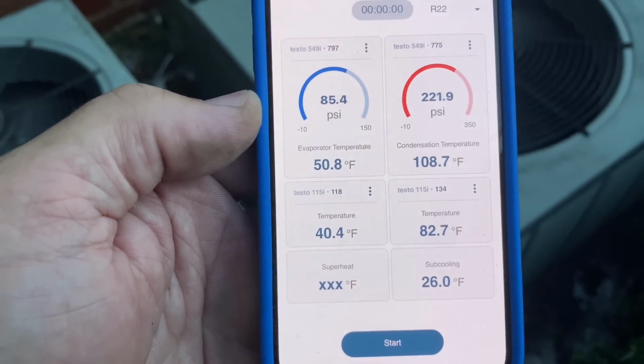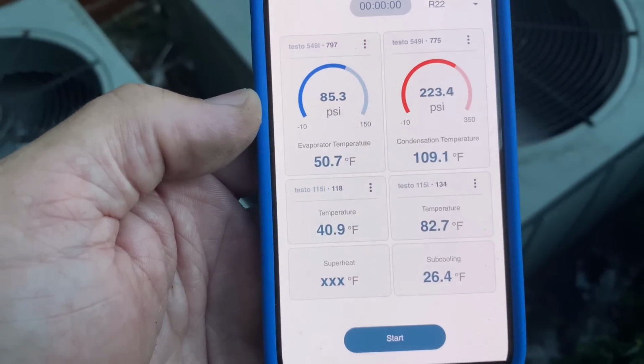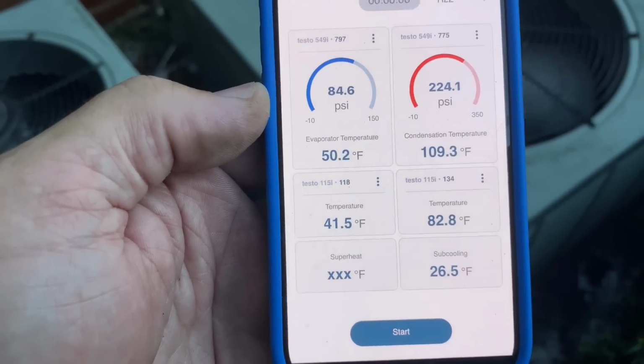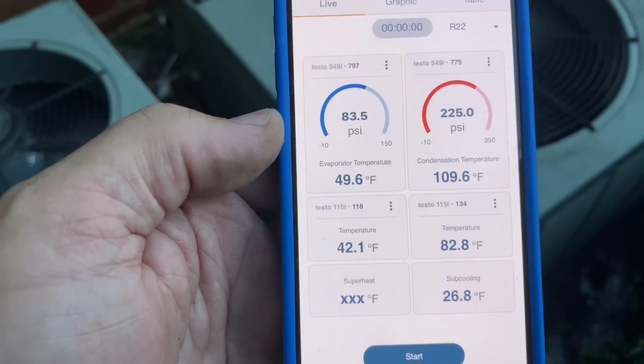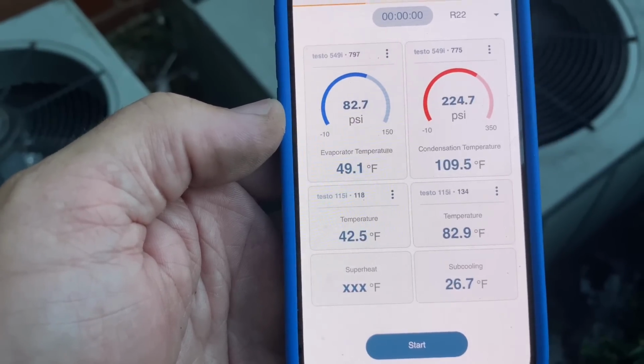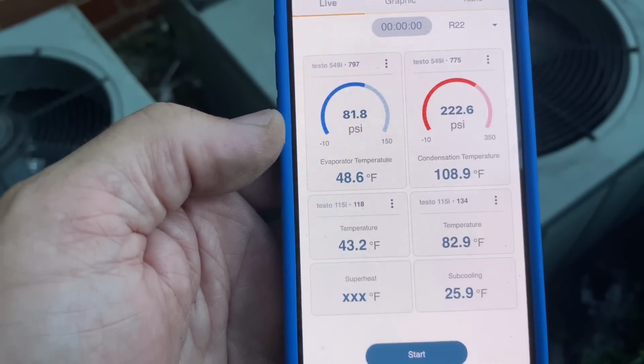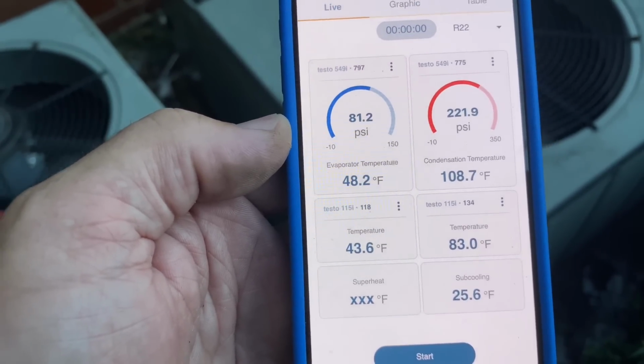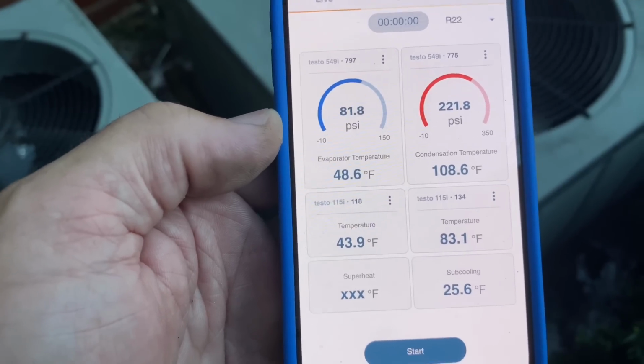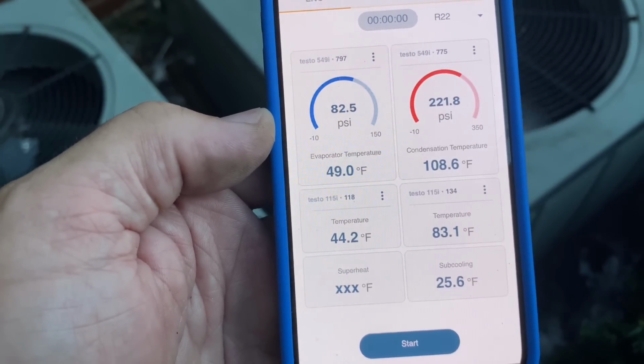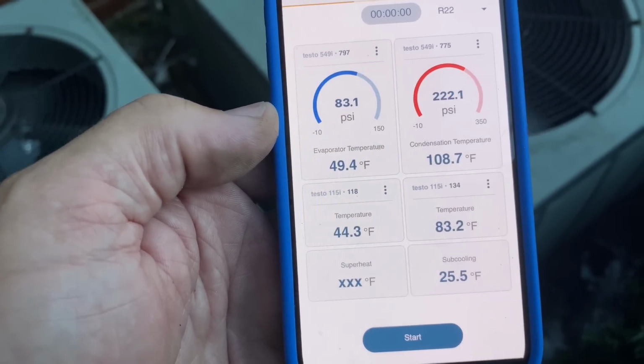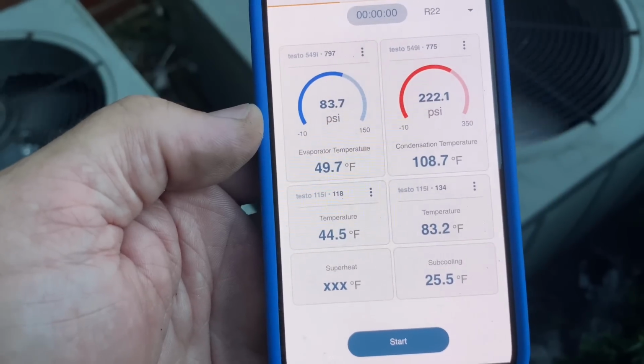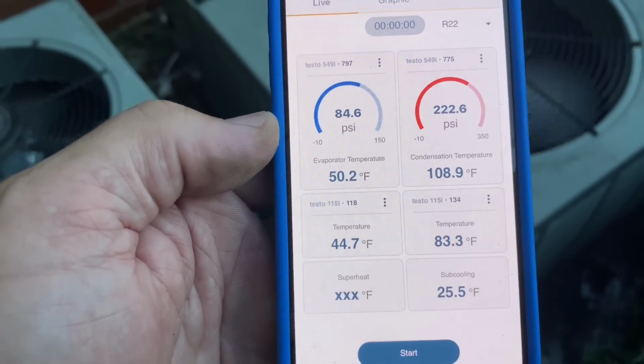Well, I'm going to let this sit for a little bit and see what happens. But I don't think we have a TXV on the system - it's probably a fixed orifice, like a meter, like a piston. I highly doubt there's a TXV on the indoor unit. No superheat. It is what it is.